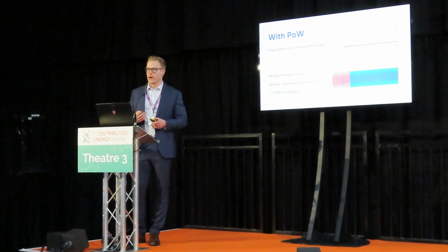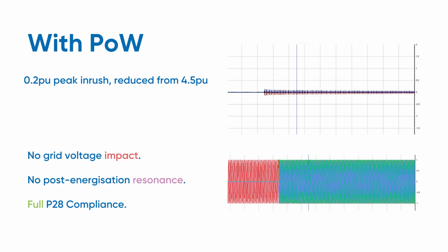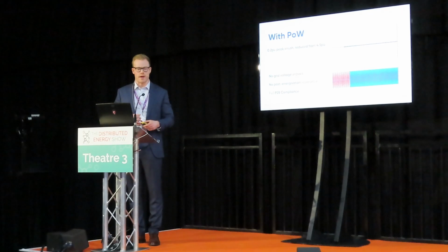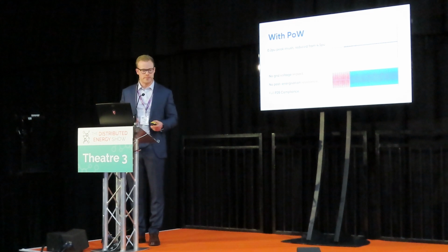Now, when you commission the point-on wave and you put the point-on wave in service, this is the type of result that you get. That's the exact same graph at the exact same scale, but this time with point-on wave switching. And we achieved around a 0.2 per unit inrush current, which is a massive reduction from the 4.5 that you get without point-on wave switching. And once again, the exact same graph, same scale. That's the voltage. You can see there's effectively no impact of switching the transformer. So this is the idea. We now use point-on-wave switching to switch every transformer, and this is the impact we have on the Shetland's 33 kV network each time, making full P28 compliance and not causing any disturbances on the network.